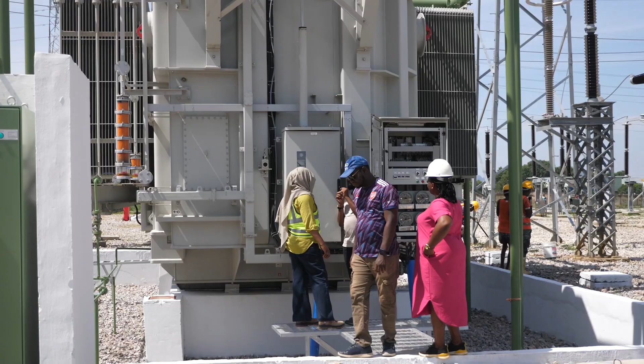The upstream is 2 by 150, which is about 300 MVA, and the downstream is 3 by 60, which is 180. So if you combine the upstream and downstream, we're going to get like 480 MVA. The expectation for this is about 0.9 power factor. You get almost 400 megawatts to be evacuated in a normal situation. But right now you need to look at the load demand of Bauchi and the environs. I think Bauchi at maximum capacity can take up to about 60-70 megawatts.